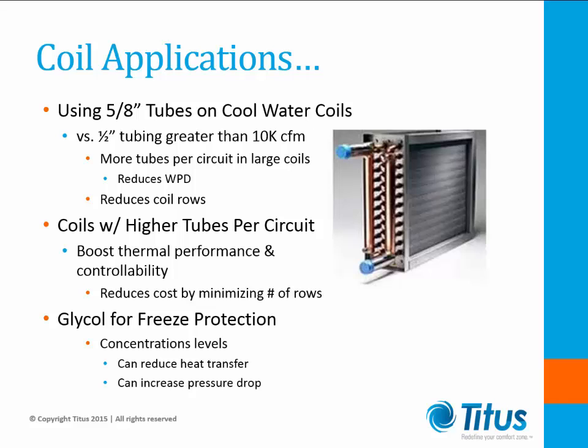On the topic of coils and their applications, let's take a look at a couple of different diameters used within coils. The half-inch tubes are usually less expensive and typically the base starting point for coil design. Selecting chilled water coils with 10,000 CFM or higher allows 5/8-inch tubes more choices in saving cost and potentially saving space within the cabinet. When larger coils use 5/8-inch tubes, it allows for more tubes per circuit without extreme water pressure drop. This may allow fewer coil rows, saving money and space.